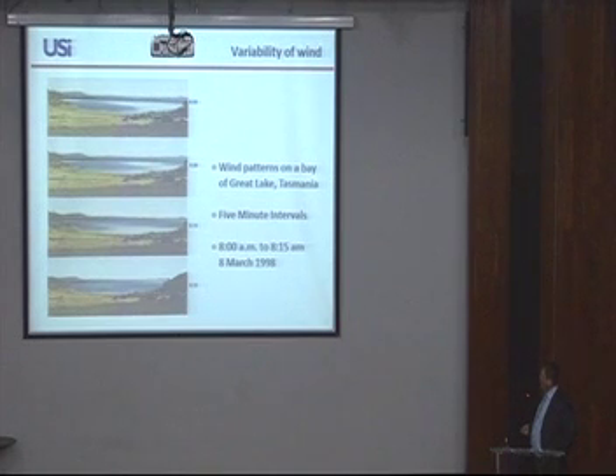And 10 to 15 minutes, that's the time constant of a conductor. That means that's the time a conductor needs to react to any change in ambient conditions. So if you imagine there's a transmission line in this area, the transmission line will see completely different wind conditions within one time constant.